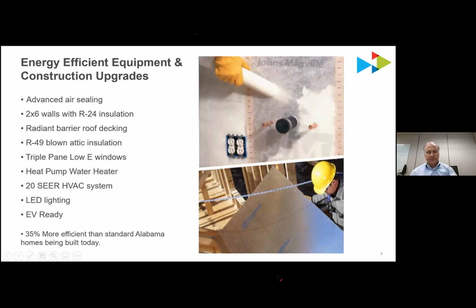For example, on a cold day in January, there was a 24-hour period where the temperature never got above 32 degrees Fahrenheit. Typically in that environment, a heat pump can't get enough heat out of the air to deliver it to your home, and it has to turn on strip heat—resistance heat inside the device—to bring the temperature up. These devices never had to turn on that strip heat, which are big energy users, and just ran off the compressor throughout that whole 24-hour period. It really changes the load shape of a home.